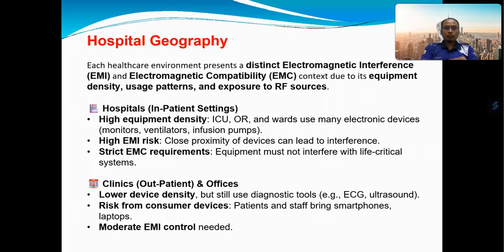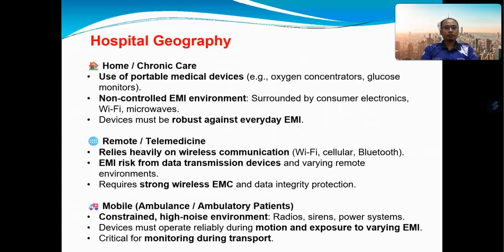There is still a possibility that these smartphones and laptops will interfere with the system of other medical devices, which is ECG or ultrasound. So in this clinical area, it needs a moderate EMI control compared to the hospital environment.